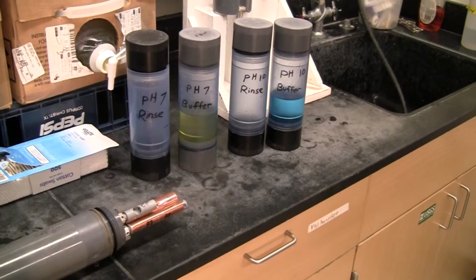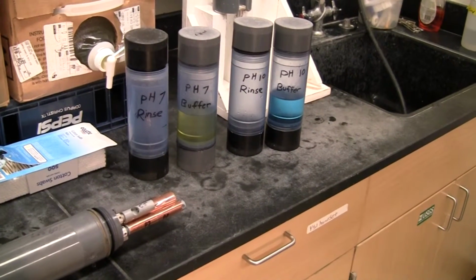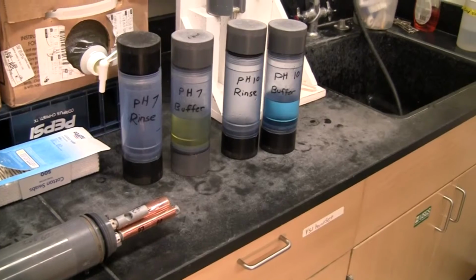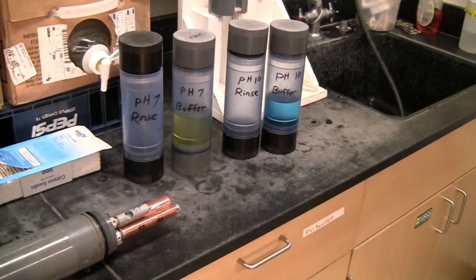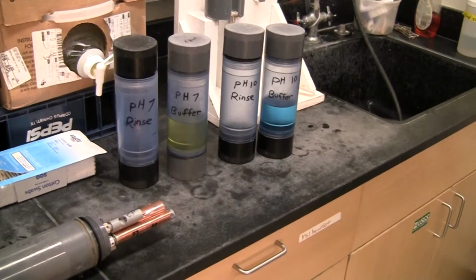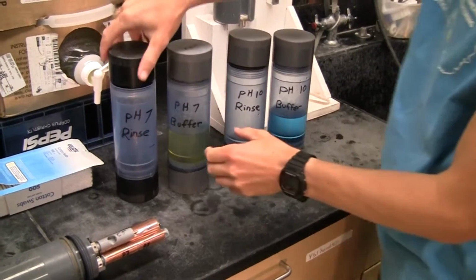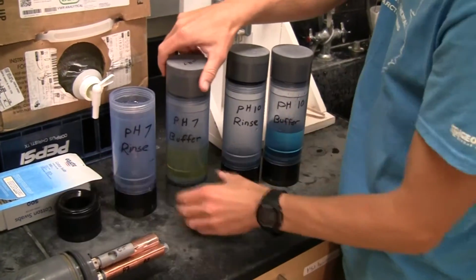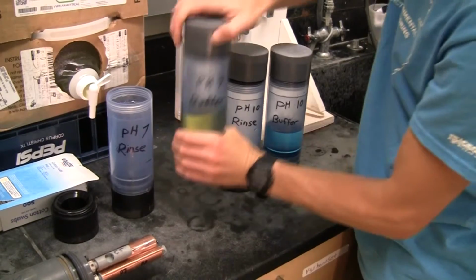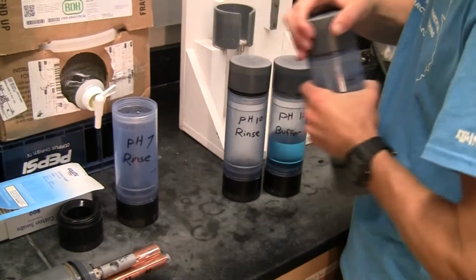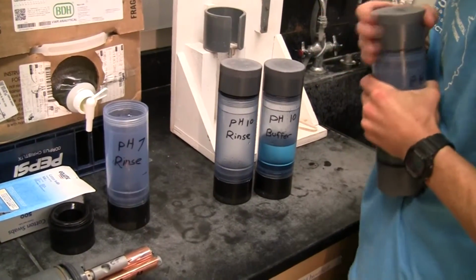For pH calibration, we're going to be doing a two-point calibration using pH 7 and pH 10. In order to do this, we have a buffer and a rinse for 7 and 10. As we located these off of the shelf, they were improperly put up. The buffer was used previously and there was no rinse. So you need to pour the buffer into the rinse.